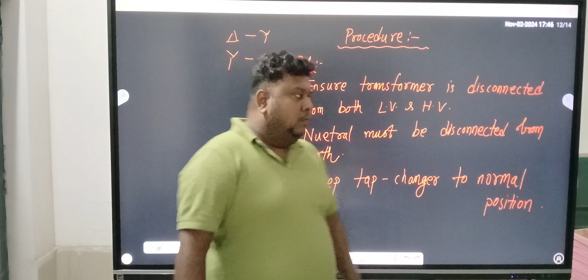Next, we have to keep the tap changer under normal position. What is normal position again for the tap changer? Tap changer, as we know, it is starting from tap 1 to whatever. Let it be, I am taking arbitrary value 25. For example, I am taking, there are 25 tappings for a power transformer. So within these 25 tappings, there will be a normal tapping. Normal tapping means, for example, that will be tap 13. Why it is called as normal tapping? Because it is as per the rated value of the transformer.